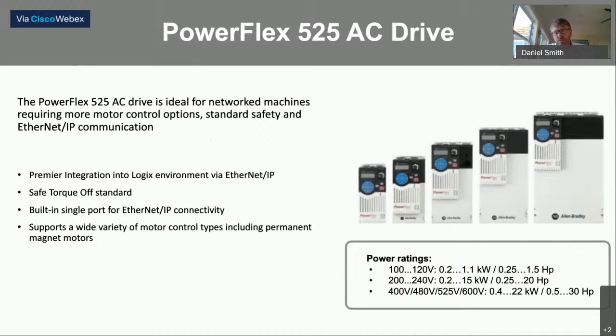Also, the difference in the 525 is it has more motor controls. It does volts per hertz, sensorless vector, as well as running permanent magnet motors. And again, the power rating is the same. It goes from fractional horsepower all the way up to 30 horsepower. Next slide.